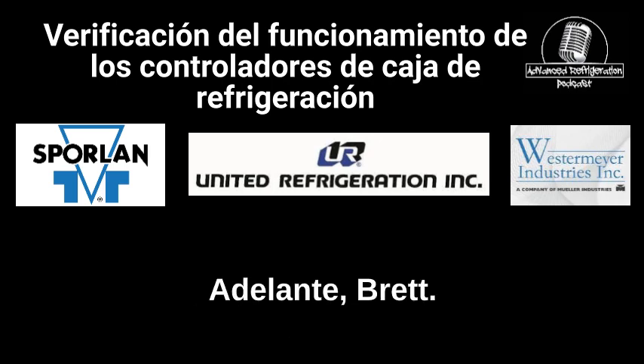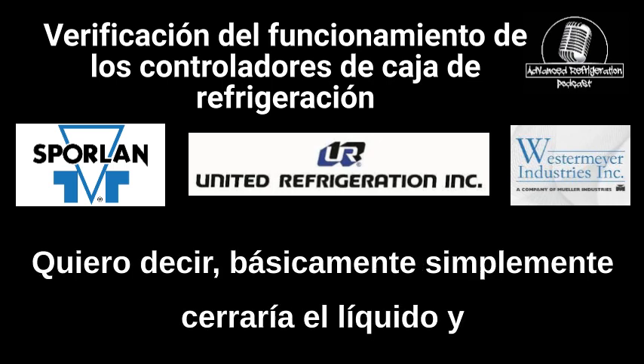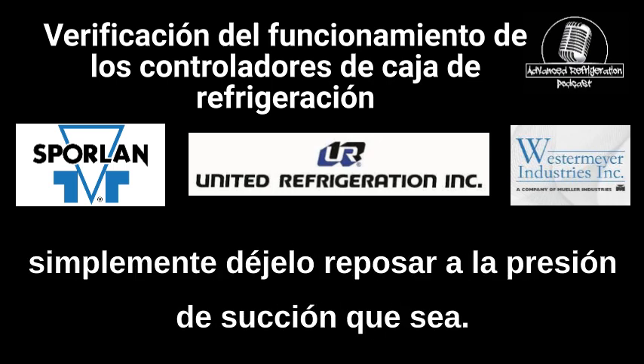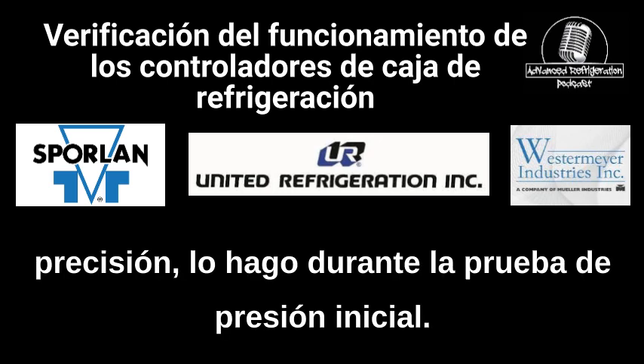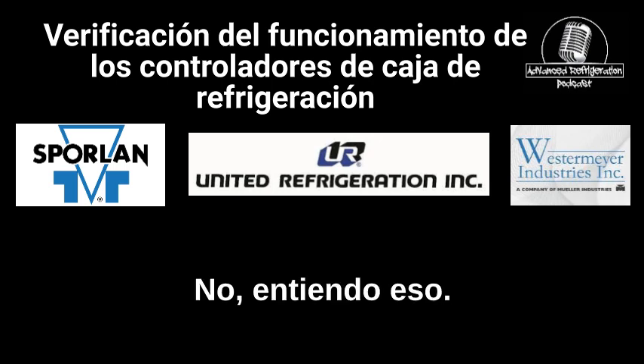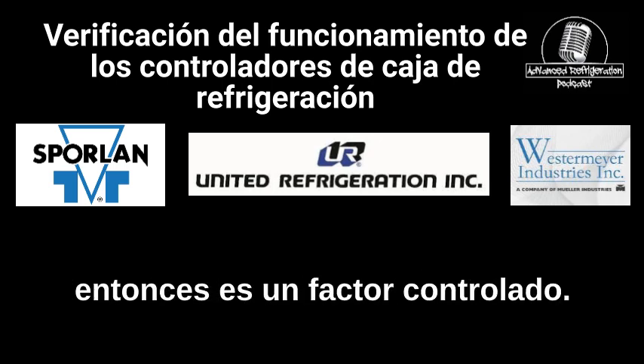Go ahead, Brett. Would you rather? This is what I would do. I basically would shut off the liquid and just let it sit at whatever the suction pressure is. Yeah, so when I check transducers, when I check their accuracy, I do it during the initial pressure test. No, I understand that. And that makes total sense because then it's a controlled factor.